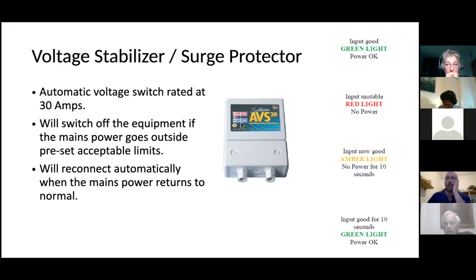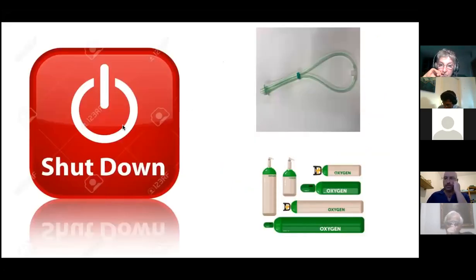An important point regarding the electricity: if the power is off, this is an emergency, because we connected the baby to the machine. We occluded his nasal airway, but the machine is not working because there is no power. So we have two options: either connect the RAM cannula directly to the oxygen container that should be in the room, or take the prongs away from his nose. But we cannot leave a baby connected to a non-functioning machine, because it will disturb his work of breathing and not assist him.